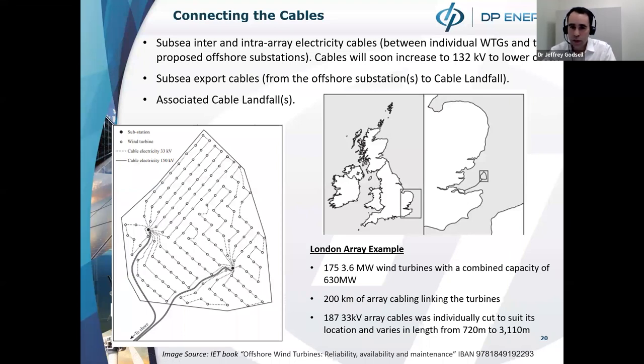The configuration of these varies, and there's no one set design. You might have 6 to 8 turbines per string, could go as low as 4, depending on the optimization for the site. The voltages, traditionally 33 kV, are increasing to 66 kV and could double again by the end of the decade.